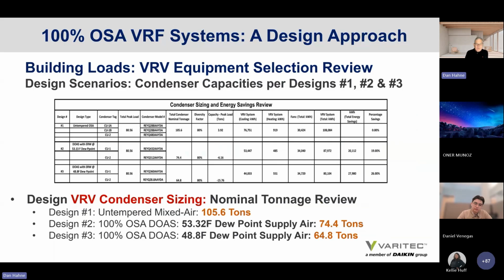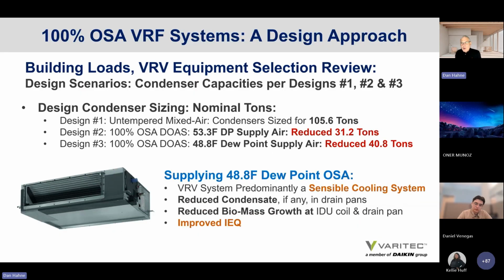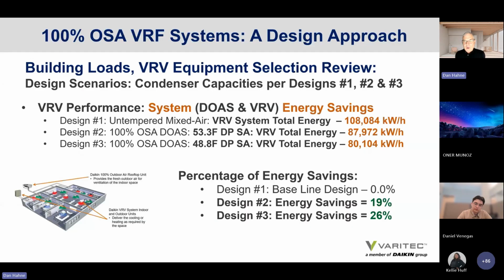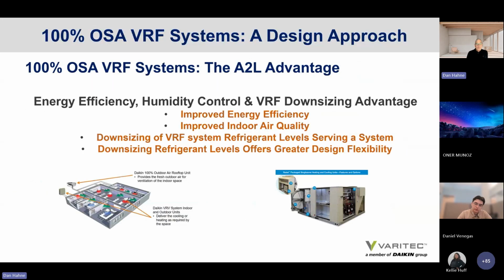And what did we find? We found that the total tonnage of these systems was significantly less than the untempered solution, which means the volume of refrigerant serving occupied zones is significantly reduced, allowing designers greater flexibility to apply A2L refrigerants if they use this design strategy. So you can see that if we use low dew point depression, there's a significant percentage of savings in overall tonnage, a significant savings on the amount of refrigerant serving these systems. Consequently, a designer will have greater flexibility in designing to A2L refrigerants. And not to mention, an owner has a day two advantage of greater energy efficiency by using a low dew point DOAS solution. So be aware of that.